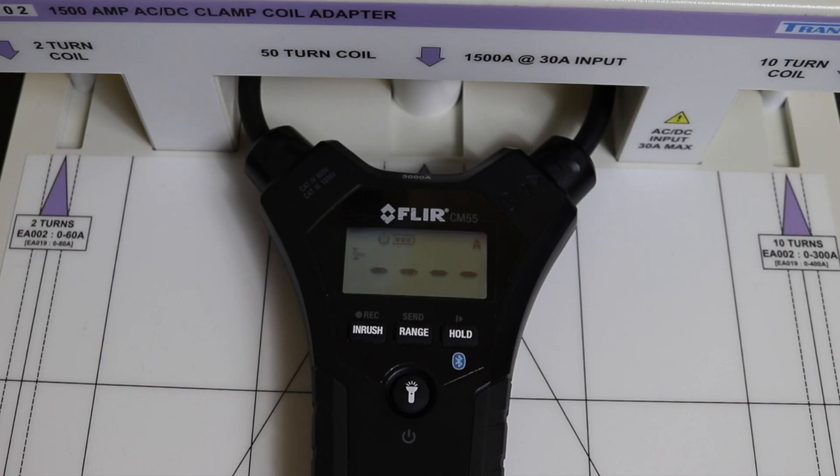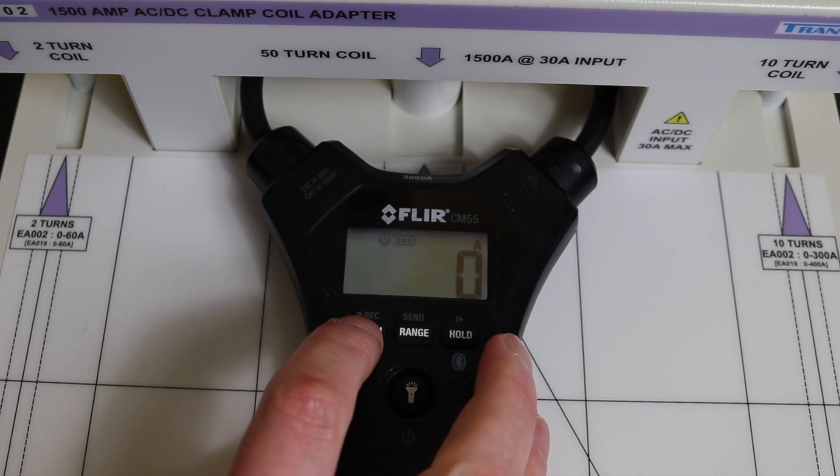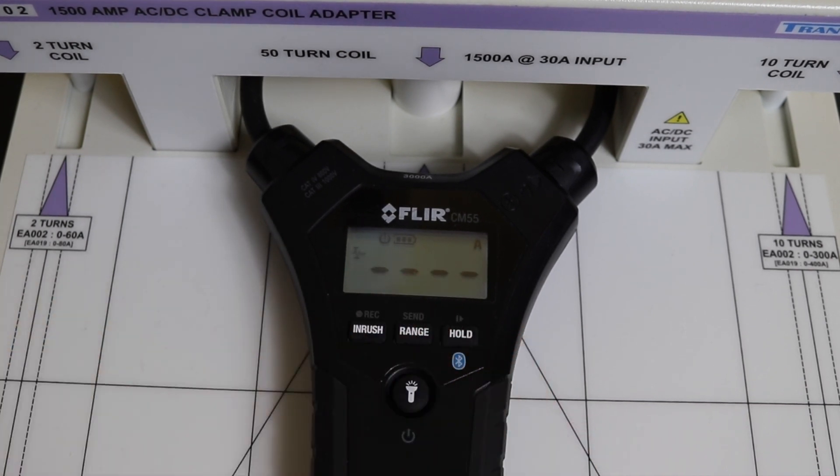Setting up the FLIR CM55 — this was the most troublesome instrument from the first video. At 350 amps AC we pick up 323 amps, which is considerably low. On DC we get only 130 amps, which is really problematic. We kind of accept the DC issue with it being a Rogowski-style coil, but the AC 50 hertz measurement is still lower than expected.